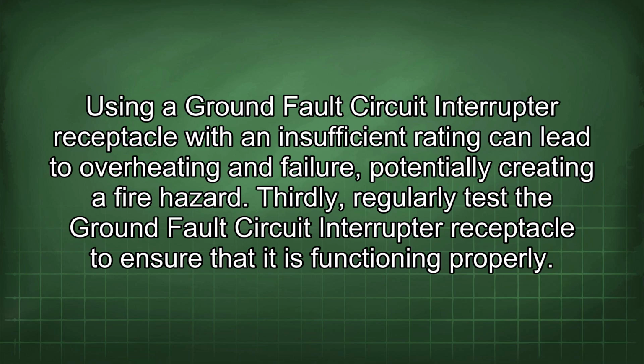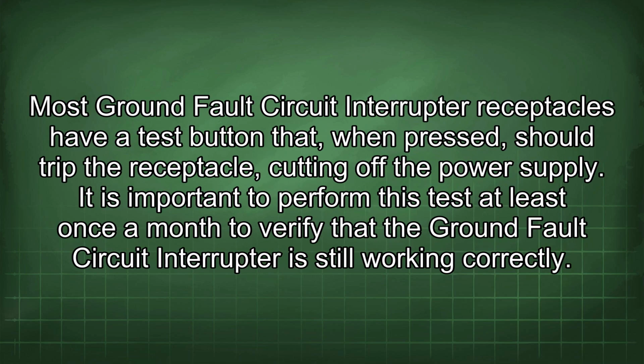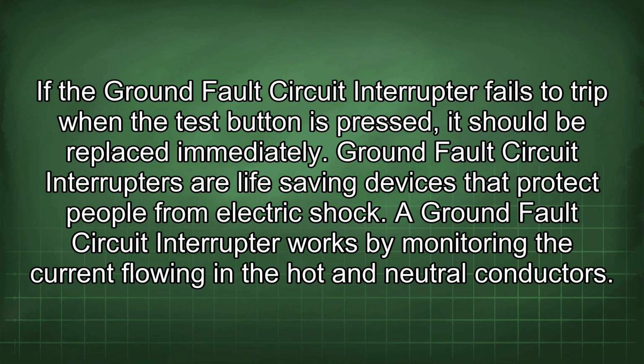Thirdly, regularly test the ground fault circuit interrupter receptacle to ensure that it is functioning properly. Most ground fault circuit interrupter receptacles have a test button that, when pressed, should trip the receptacle, cutting off the power supply. It is important to perform this test at least once a month to verify that the ground fault circuit interrupter is still working correctly. If it fails to trip when the test button is pressed, it should be replaced immediately. Ground fault circuit interrupters are life-saving devices that protect people from electric shock.